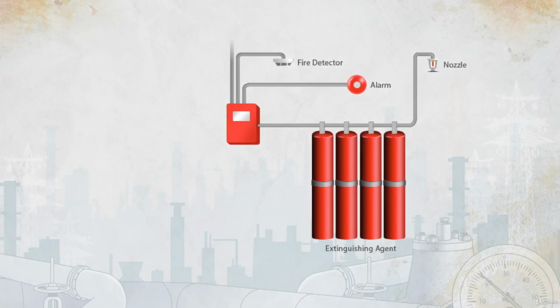Fixed fire extinguishing systems throughout the workplace are among the most reliable firefighting tools. These systems detect fires, sound an alarm, and then send water to the fire and heat. In order to meet OSHA standards, when a fire extinguishing system is down for service, employers must temporarily substitute a group of trained employees to act as fire watch to respond to fire emergencies. Employers must also ensure that the fire watch is included in the fire prevention plan and the emergency action plan, and post signs and placards for systems that may use chemical agents that are health hazards.